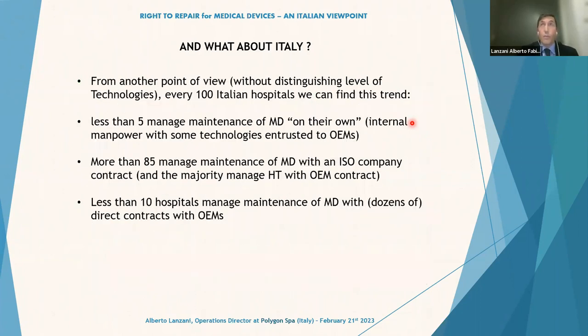From another point of view, if we make a statistic, out of every 100 hospitals, we find this kind of trend. Less than 5 manage maintenance of medical devices on their own, with internal personnel and some contracts with OEMs. More than 85 hospitals manage maintenance with an ISO company contract. The ISO company could, if it wants, also establish OEM contracts for lower or higher technology. Then you have less than 10 hospitals that manage maintenance by making dozens of contracts with all the manufacturers they have.